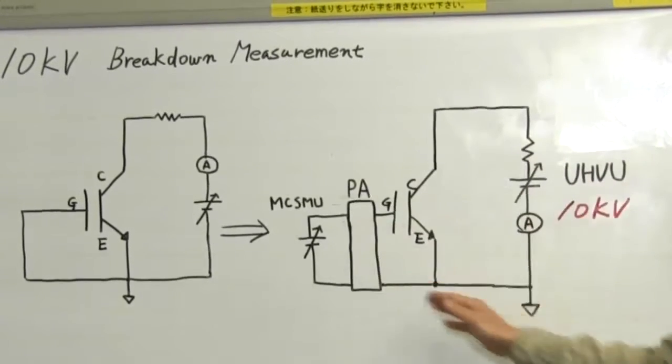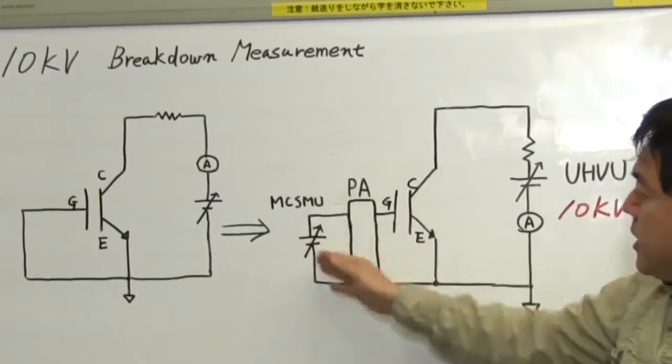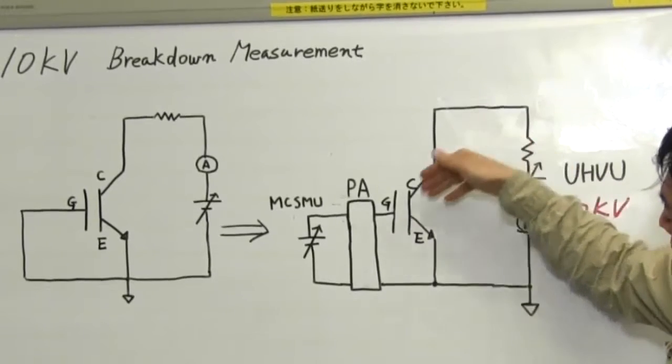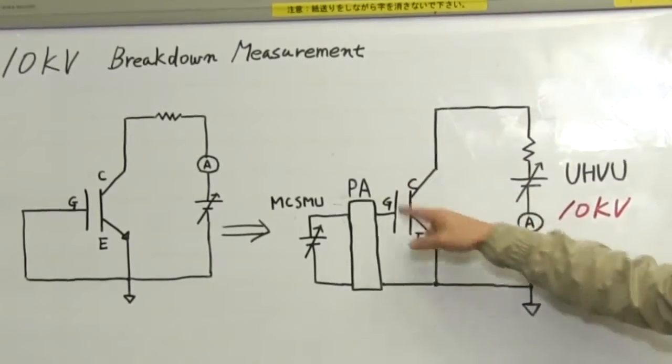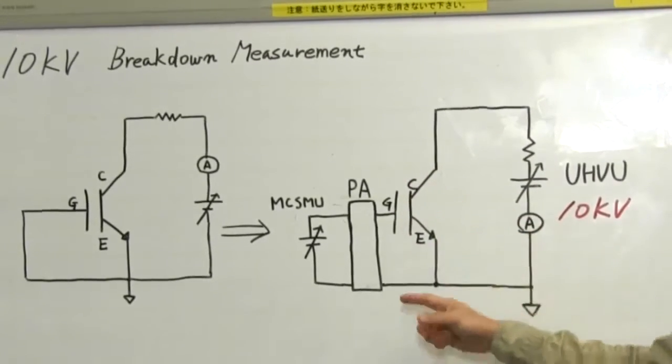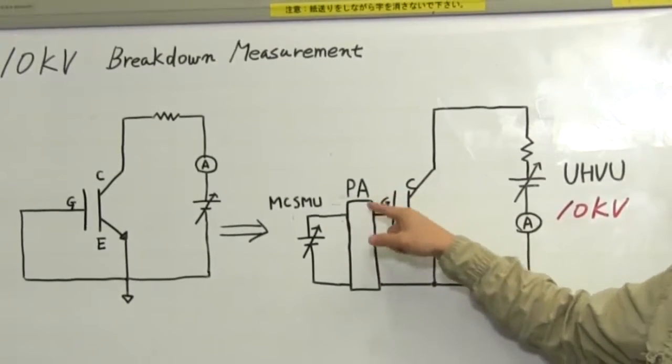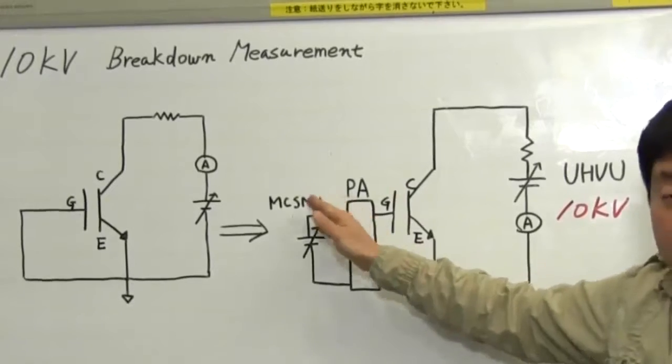And during measurement to protect medium current SMU from such voltage or current when device is broken, we have developed special protection adapter for MCSMU.